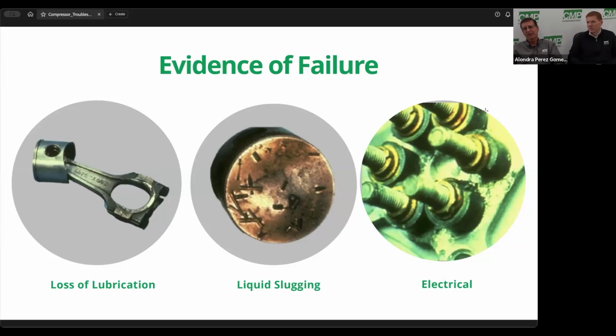And sometimes it doesn't require maybe an hour. It depends on how large the system is, but just think of what you're trying to do: just removing the non-condensables. And once you do that, if it's a regular conventional system, you can pretty much charge it up right through the discharge line or liquid line. You can put most of your refrigerant in that way.